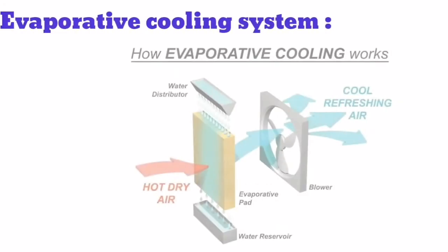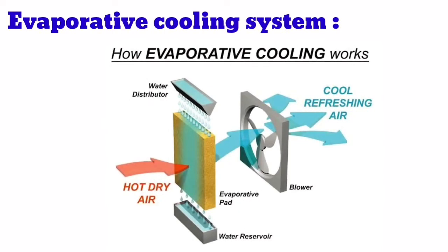The third type of system is known as an evaporative cooler, or a swamp cooler — sometimes called nature's air conditioner. Just as a breeze across wet skin provides cooling as moisture evaporates, an evaporative cooler does the same. Dry air is passed through porous media wetted with water; as the air contacts the water spread over the media, much of the water evaporates. It is normally found only in very hot and dry climates. Air is drawn into the cooler by a blower and passes over an absorbent pad, which is continuously soaked with water.